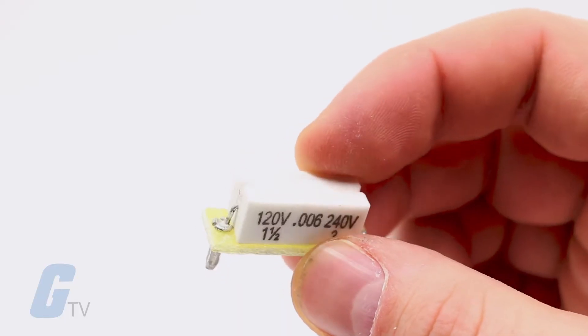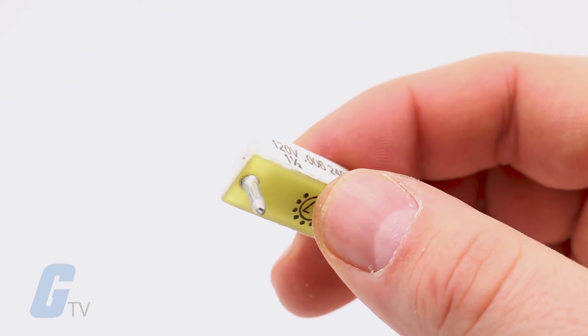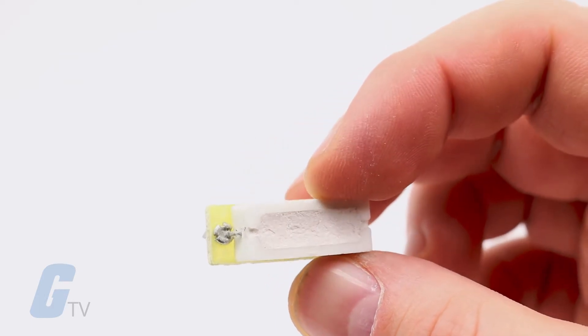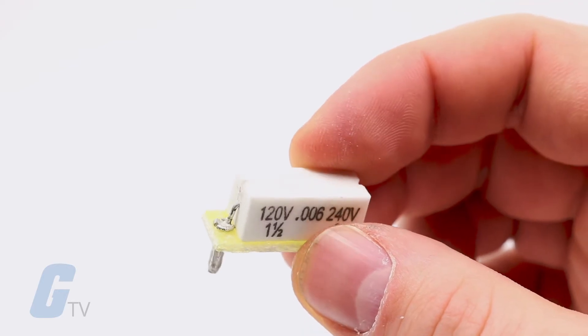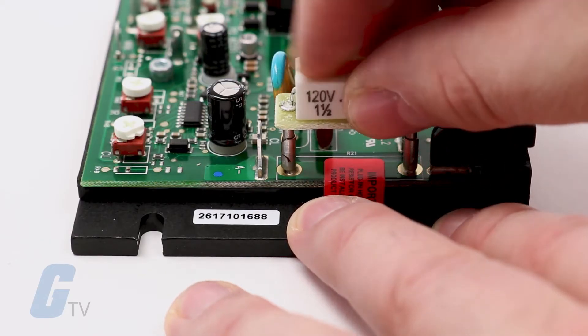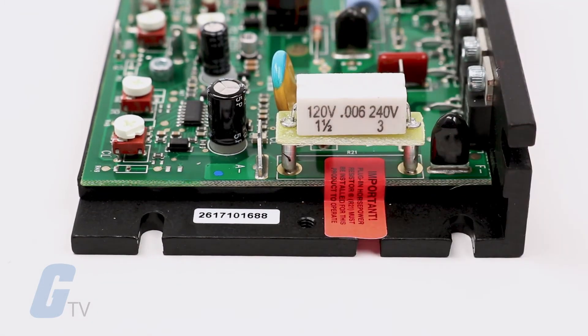A unique feature of the KBIC Controls is the plug-in horsepower resistor. This accessory is a requirement to operate the drive and should be purchased according to your motor's horsepower. To install, I can simply plug in my horsepower resistor with the port here between the A- and F- terminal.